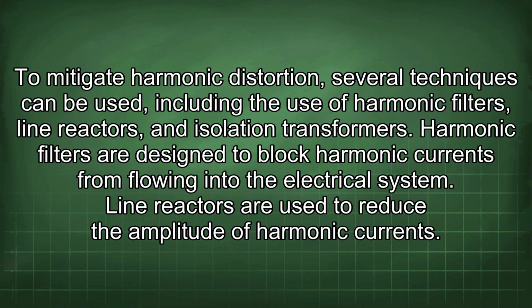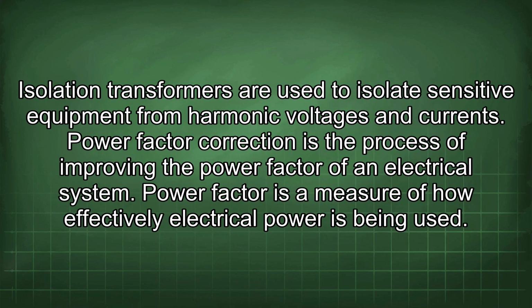To mitigate harmonic distortion, several techniques can be used, including the use of harmonic filters, line reactors, and isolation transformers. Harmonic filters are designed to block harmonic currents from flowing into the electrical system. Line reactors are used to reduce the amplitude of harmonic currents. Isolation transformers are used to isolate sensitive equipment from harmonic voltages and currents.